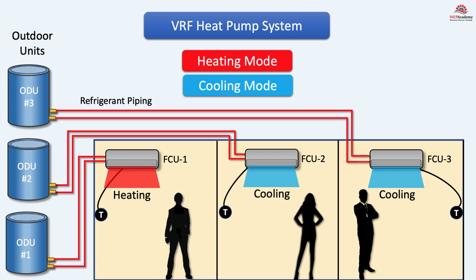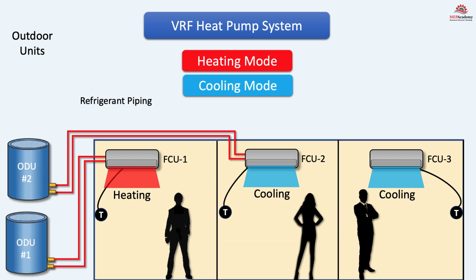To reduce the number of outdoor units, the engineer will group together those zones that have similar load profiles. So, indoor fan coil number 2 and 3 have similar load profiles, so we can get rid of one of the extra outdoor units and its piping and connect fan coil number 3 together onto outdoor unit number 2. This saves on outdoor units.